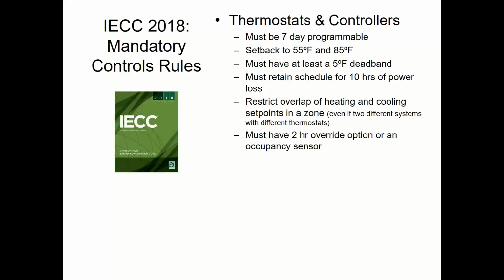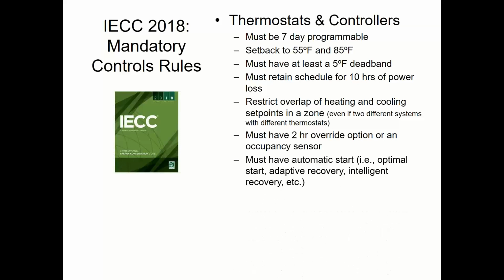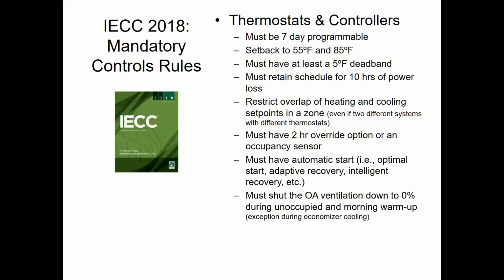You have to have a way for the occupants to override the set point. If not, they're going to bring in space heaters and jack stuff up anyway. You have to do that intelligent recovery I talked about where it starts early. That's required by code. You have to shut the ventilation damper at unoccupied times. That's required by code. And then you have to do what's called FDD, fault detection and diagnostics. I'm going to show you that on the economizer discussion, but the thermostat has to be part of that discussion.